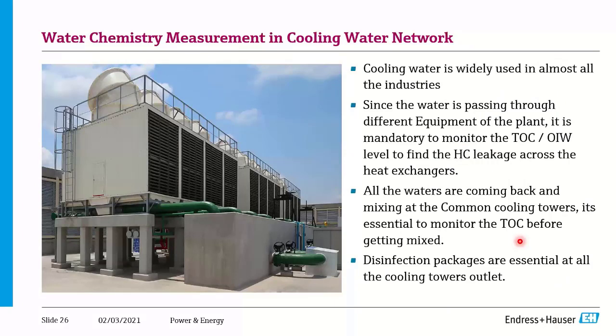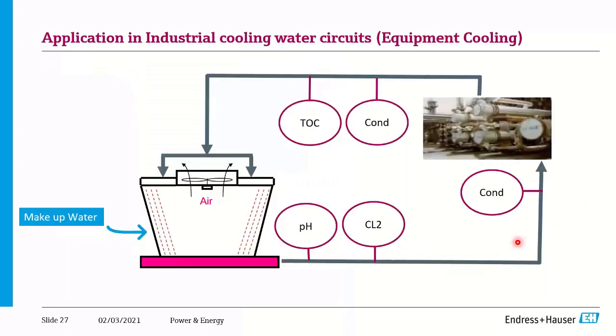Water chemistry measurement in the cooling water network is very crucial because cooling water is distributed to turbine areas, pump cooling, and auxiliary plants. When it returns, there may be chances of hydrocarbon leakage or increased total organic carbon. When cooling water leaves the cooling tower, it must be disinfected — continuously monitor pH and chlorine. At heat exchangers, monitor conductivity at inlet and outlet. Before returning to the cooling tower, always monitor TOC to verify it is within permissible range.